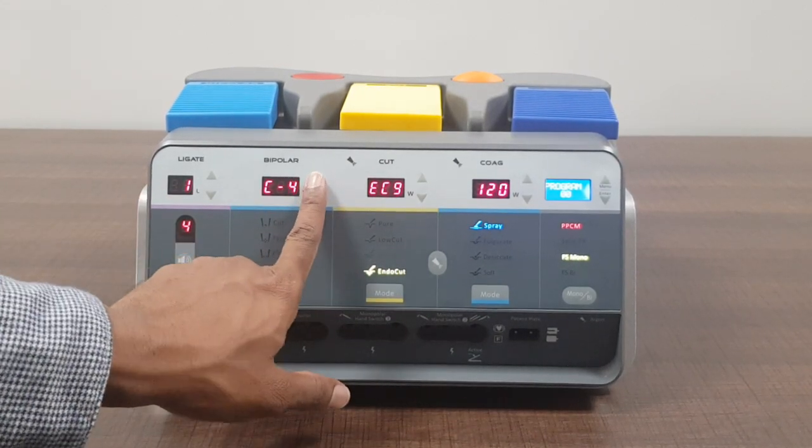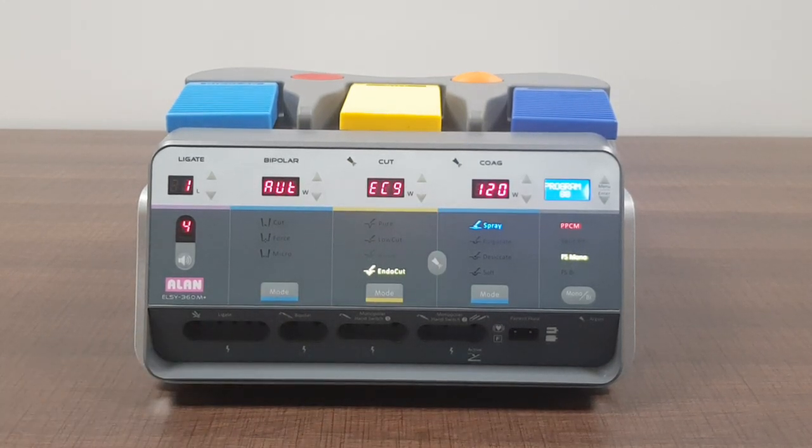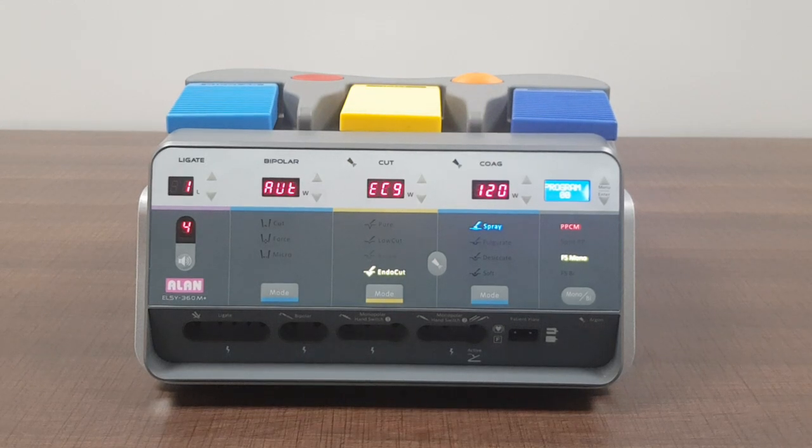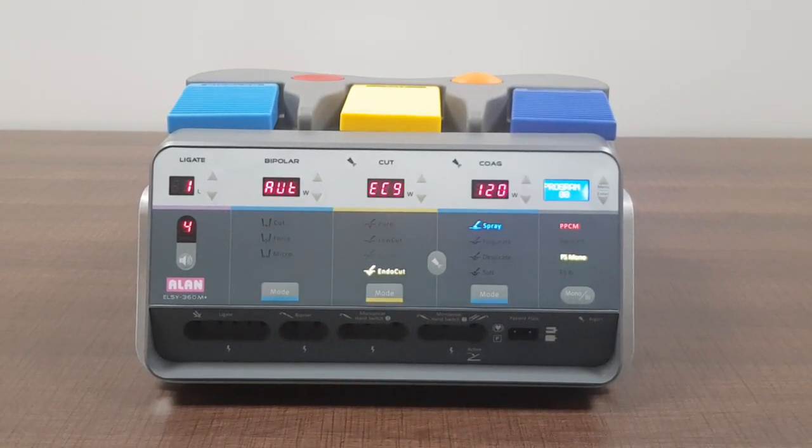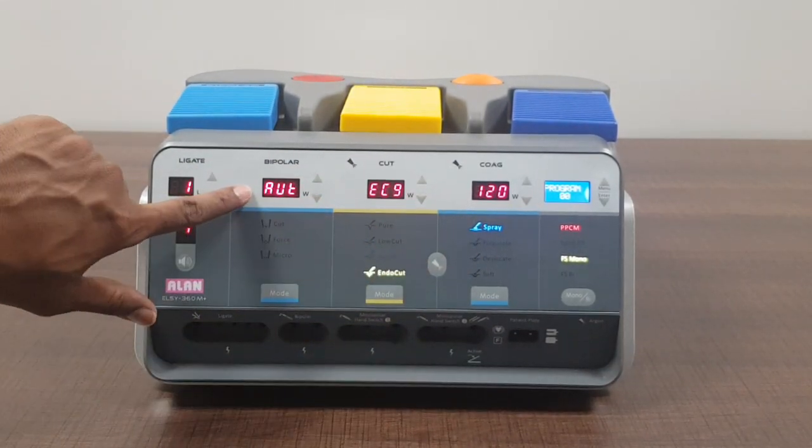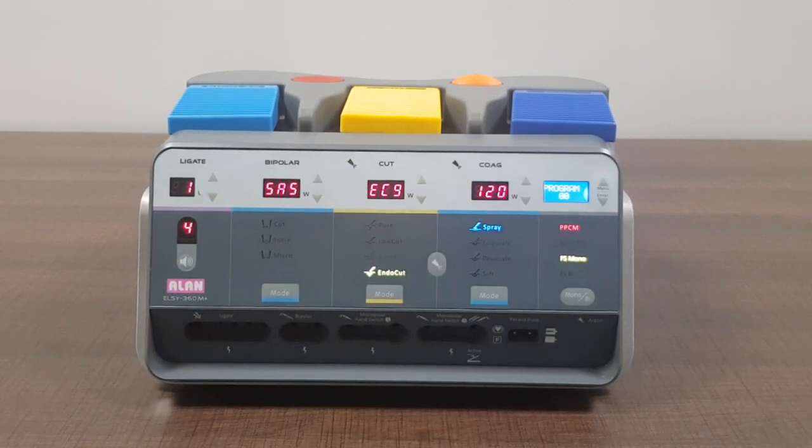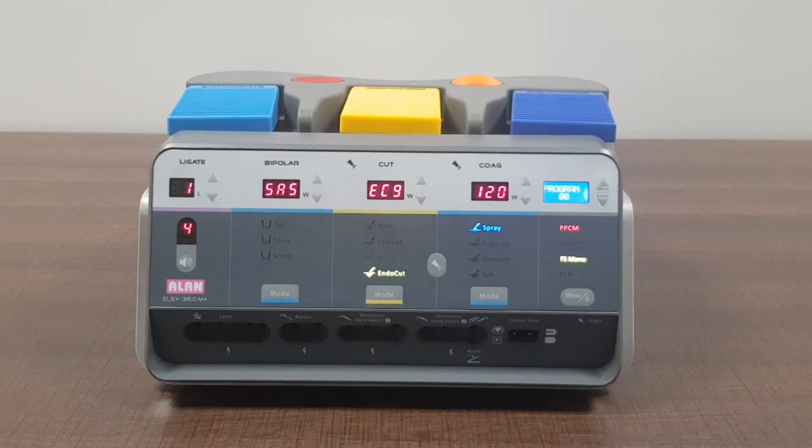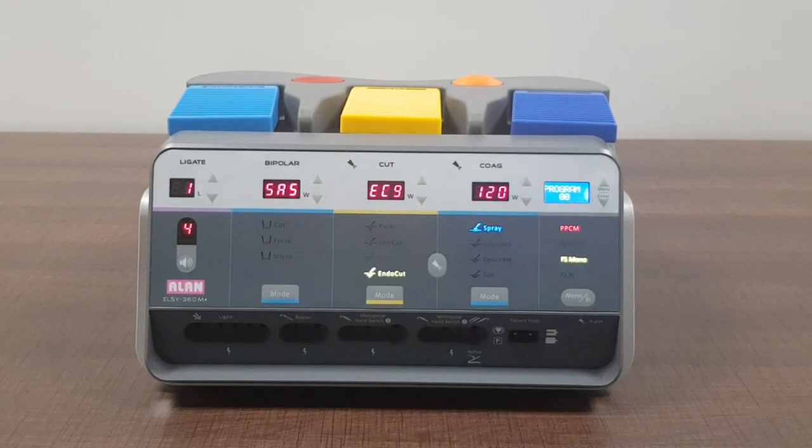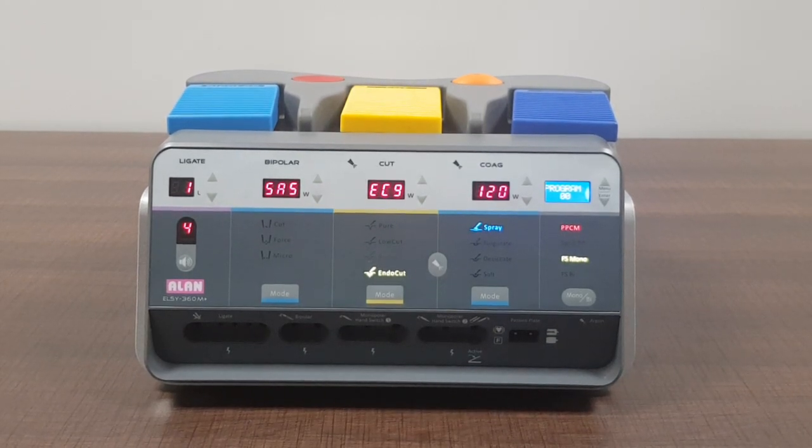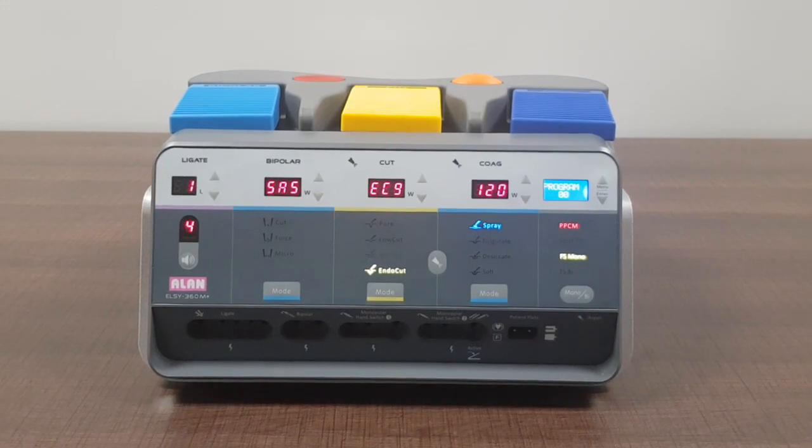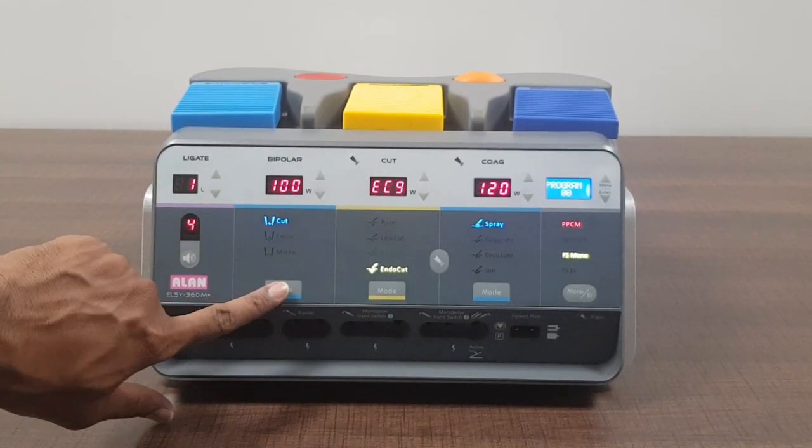Then comes auto stop which means when you turn on the coagulation in bipolar it stops automatically just like you saw it in auto desiccate and auto soft. Then comes SAS. This is auto start auto stop. When you hold the tissue between the jaws of your bipolar forceps and you press this, it will sense the tissue and it will start coagulate and then stop automatically. So there are like six modes again in bipolar.